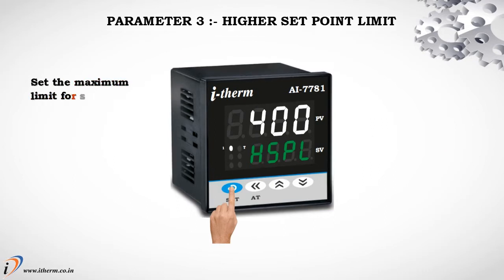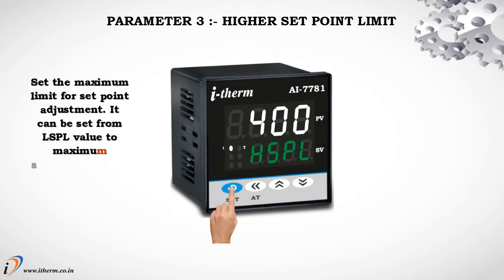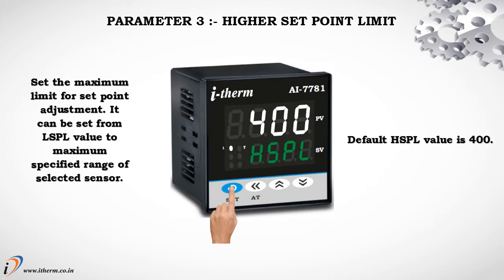Parameter 3 is Higher Set Point Limit. This sets the maximum limit for set point adjustment. It can be set from the L SPL value up to the maximum specified range of the selected sensor. The default H SPL value is 400.